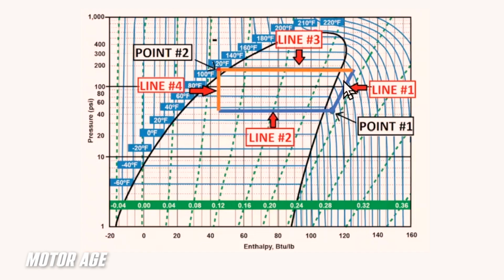In other words, we don't have to evacuate and recharge a system as an experimental step to see if it's properly charged. We can yield the information from this data, these plotted data points here, to give us some insight into system performance. In other words, we are seeing the energy in this closed loop refrigerant system as heat is exchanged both in and out of the climate around us. As heat enters the system or exits the system, it's going to produce a significant point on this chart, and where they all intersect represents the functionality of this system.